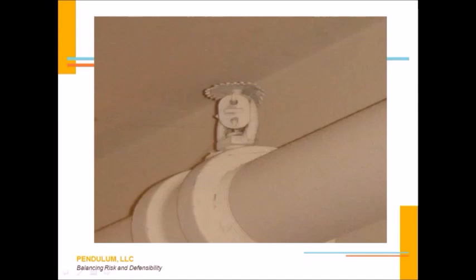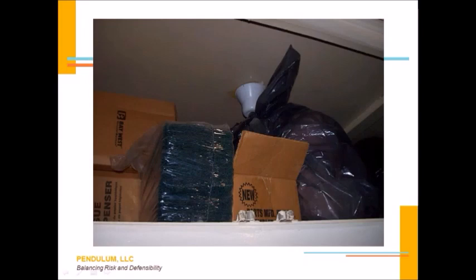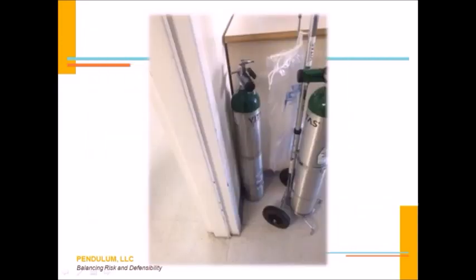When it comes to your fire sprinkler heads, particularly the heads themselves, we see a lot of painted and compromised heads in your facilities. They have to be free and clear of all foreign material, and that is corrosion and rust and other things like dust and debris and spider webs. Otherwise, you're going to get the tag from the surveyors. You've got to have that magic level of clearance beneath and around your sprinkler heads. If I were to ask the group right now to tell me what that magic number is, I know, of course, you would all say 18 inches of vertical clearance below those sprinkler heads. Make sure that they're not obstructed.